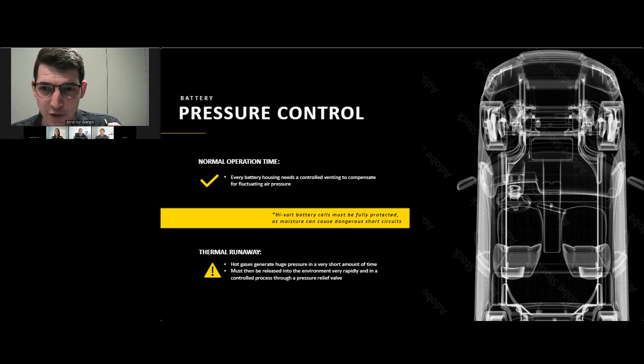For example, the one you see here features an internal membrane instead of a spring-loaded design, which reduces assembly complexity, makes it easier to handle, and enables a multiple-use functionality. This means that in case of a thermal incident that is brought under control quickly, the membrane will close again, restore a gas-tight seal, and be ready to function again in the next situation whenever it occurs. This is sometimes different with other designs, depending on how they are made.